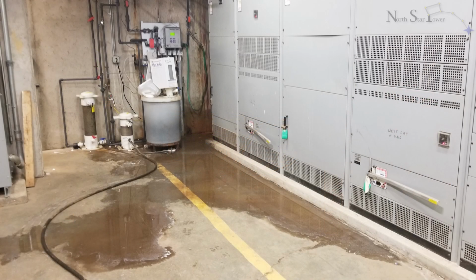What other environmental hazards might cause electrical components to quickly fail? A common culprit is the weather. In the substation room, look for signs of water leakage. Standing water on the floor, wet marks, and rust are telltale signs.